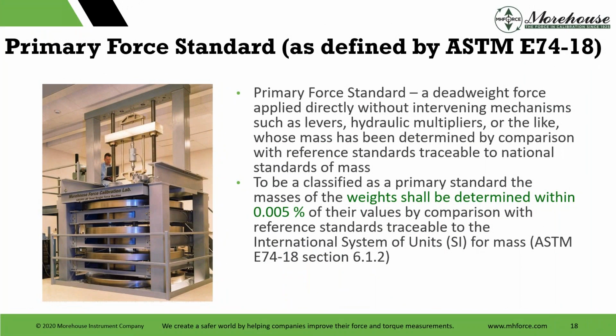So if we look at it, I said, primary force standard, the definition in E74 is a deadweight force applied directly without intervening mechanisms such as levers, hydraulic multipliers, or the like, whose mass has been determined by comparison with reference standards traceable to national standards of mass. To be classified as a primary standard, the masses of the weight shall be determined within 0.005%, that's 50 parts per million, of their values by comparison with reference standards traceable to the International System of Units.